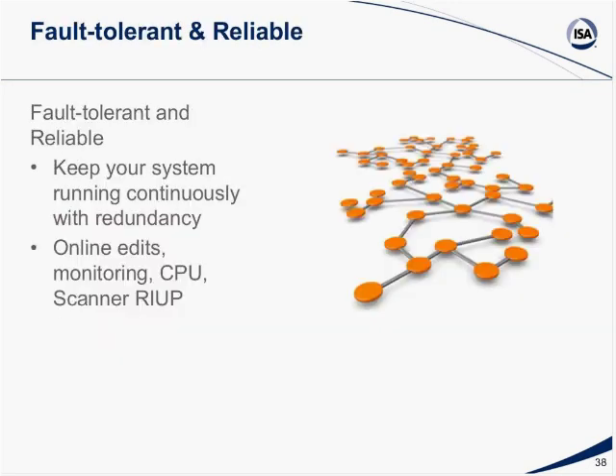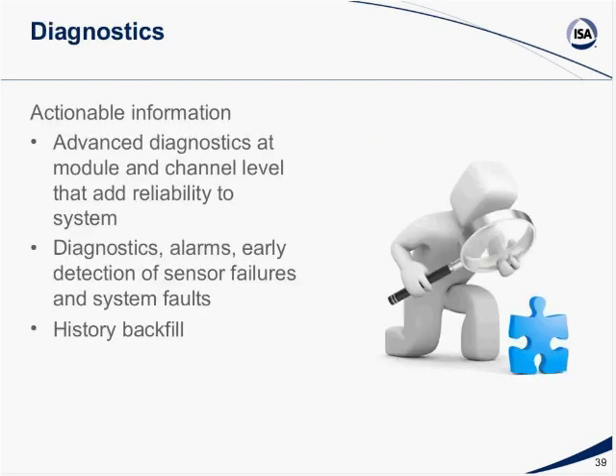You're also looking for a product that's fault tolerant as well, and we'll be looking at a system which has redundancy at least at the CPU racks, power supply, and communication level that allows customers to keep their systems running continuously. So we're looking at a system that also provides capabilities to do online configuration, monitoring, removal and insertion under power, because during startup a lot of time can be spent tweaking the design or correcting design mistakes. So this is another key aspect when you look at a process and safety system.